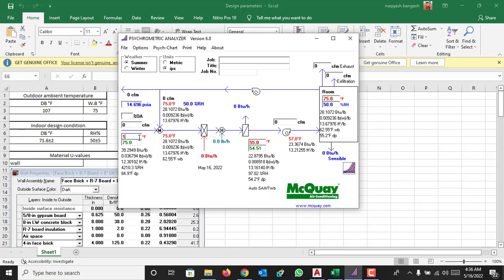So in this case it's 107 Fahrenheit dry bulb temperature and 75 Fahrenheit is the wet bulb temperature. In the next section we will see that this is the coil section, so normally the air supplied by AHU or FCU is 55 Fahrenheit supply air.